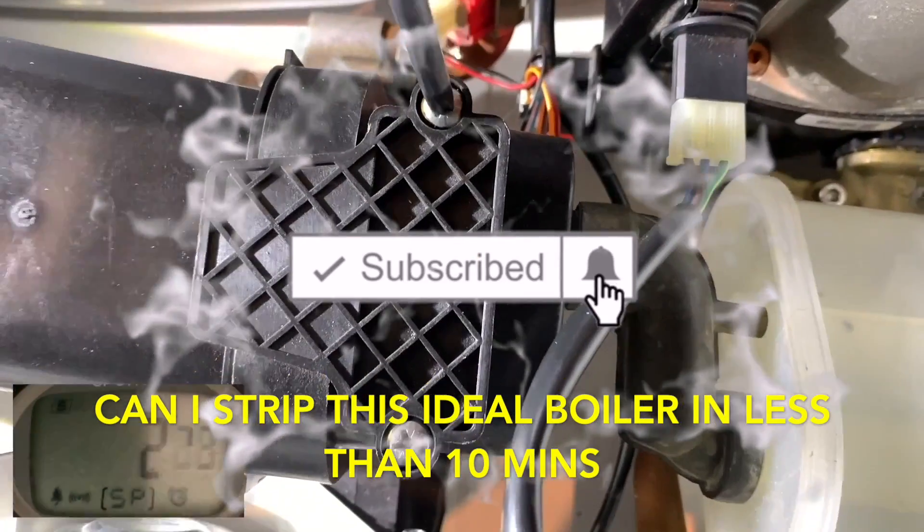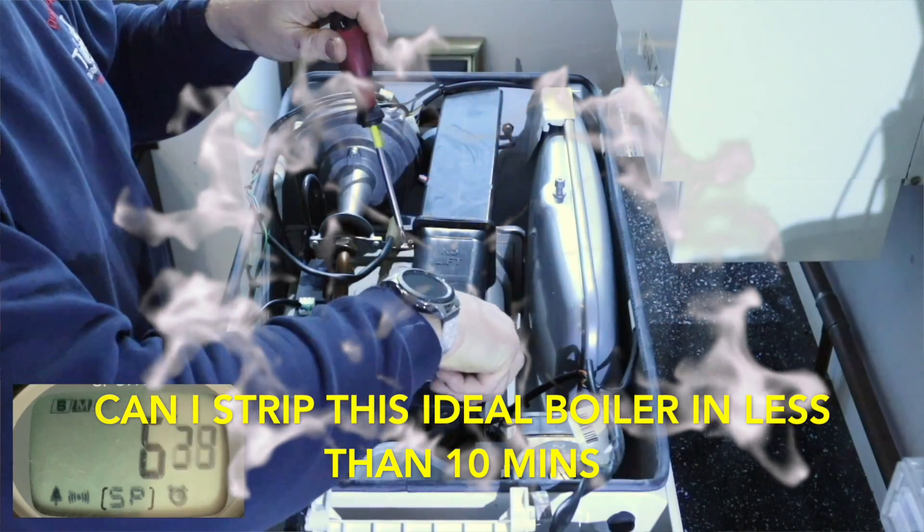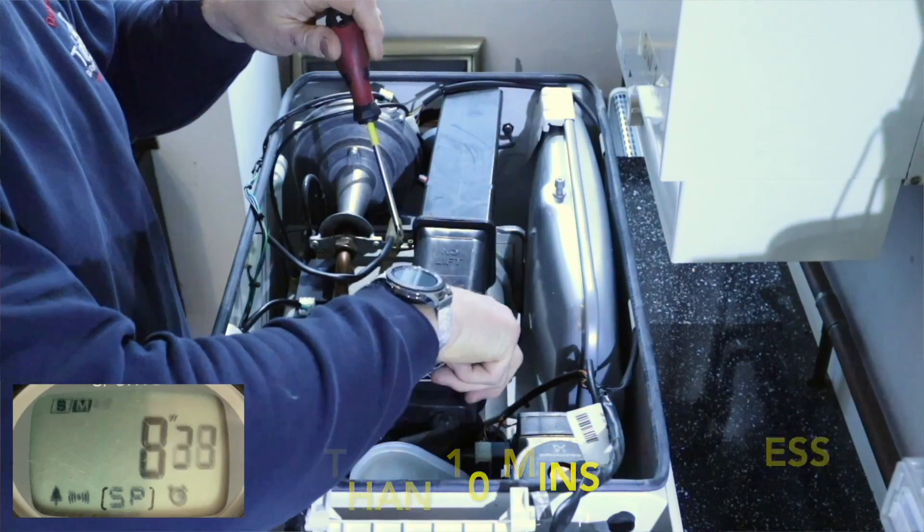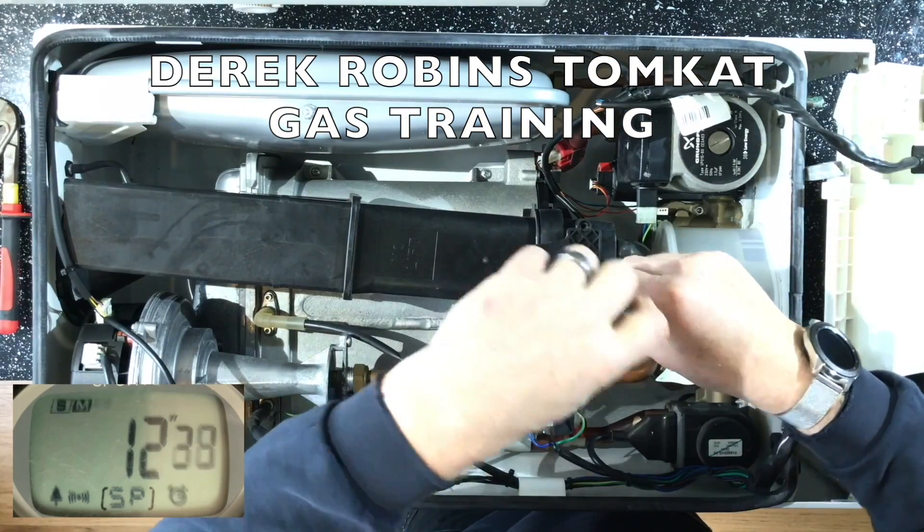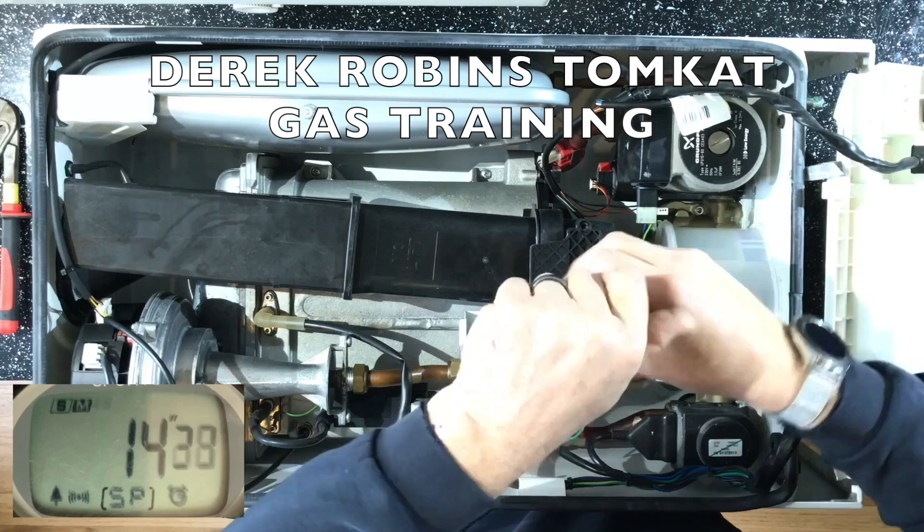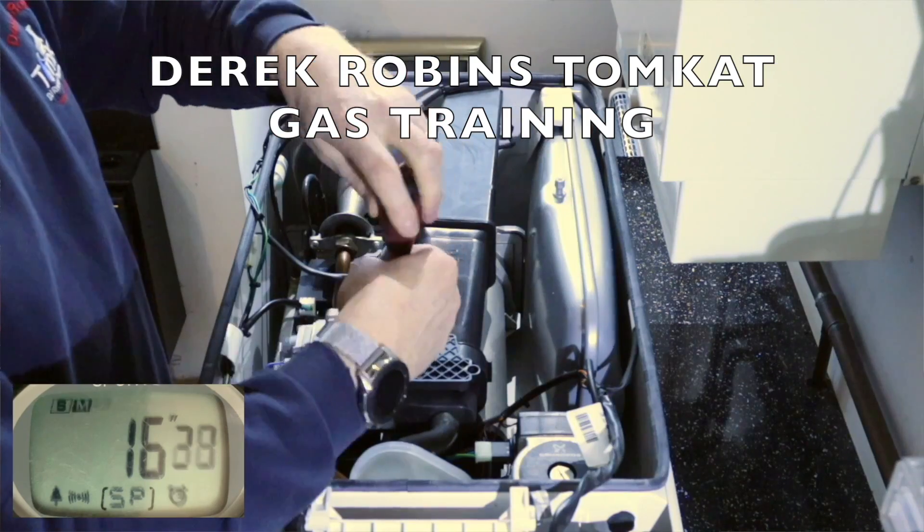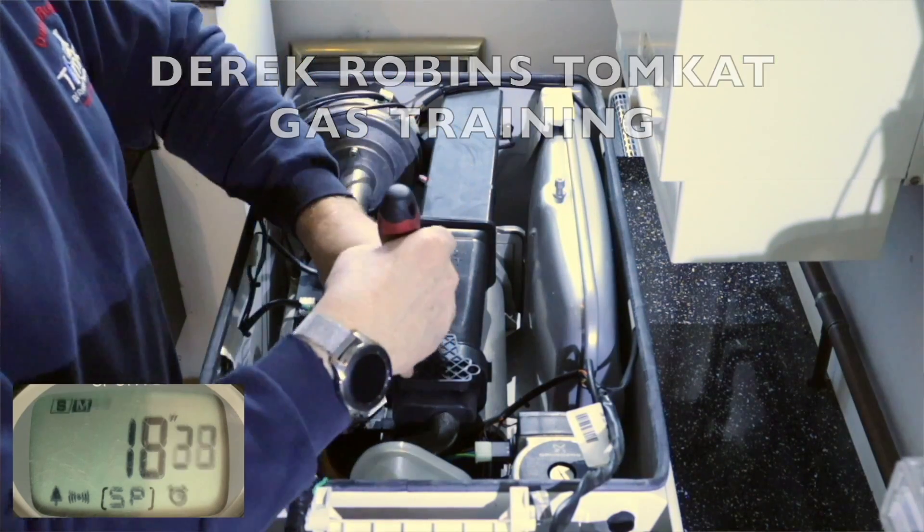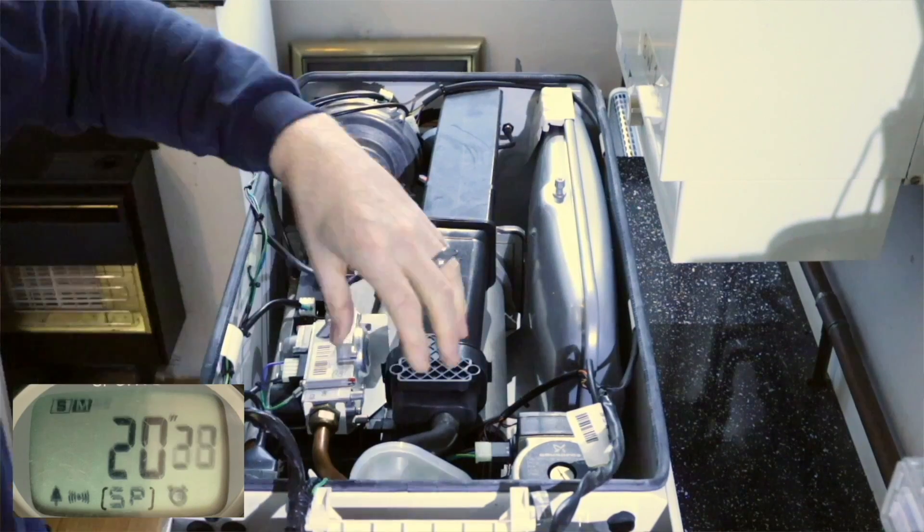Now the first thing I'm removing are these two screws, and these two screws hold the sump cover on. The sump cover allows you access into the sump when you come to service, but it also holds the flue manifold which connects the sump to the turret in position. You have to remove this cover when you want to remove the flue manifold.